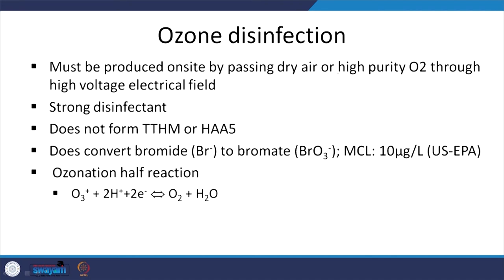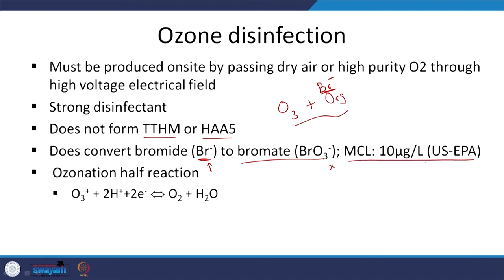Ozone disinfection: one advantage is it does not form trihalomethanes or haloacetic acids, but it does form something else — bromate — if bromide (Br⁻) is present in the water. Ozone reacts with Br⁻ to form bromate, which is toxic and possibly carcinogenic. India has no standard for bromate, but US EPA regulates it at 10 ppb, which is very low. Ozone is one of the strongest oxidizing agents — probably the second strongest — with a very favorable half-reaction as an electron acceptor.